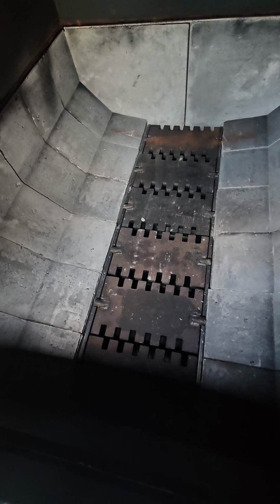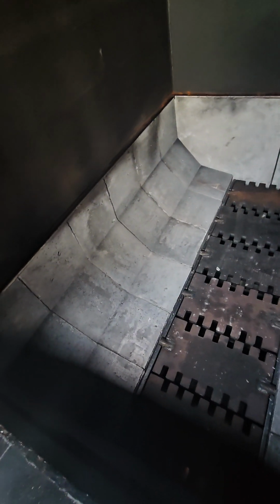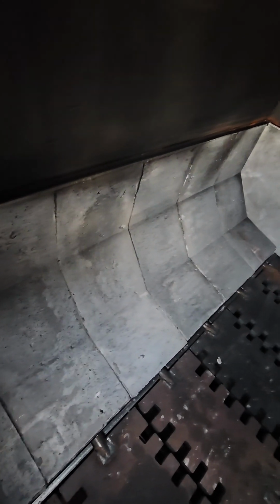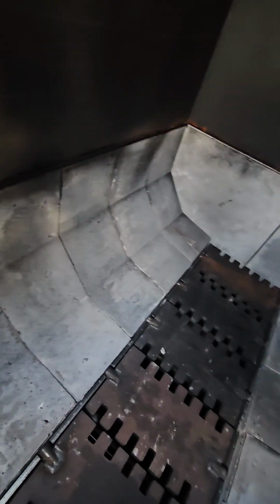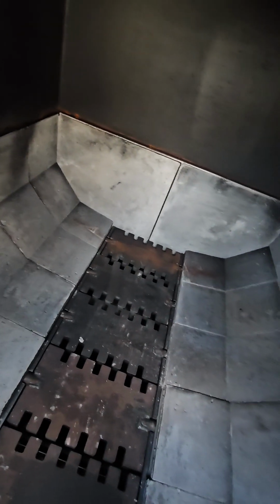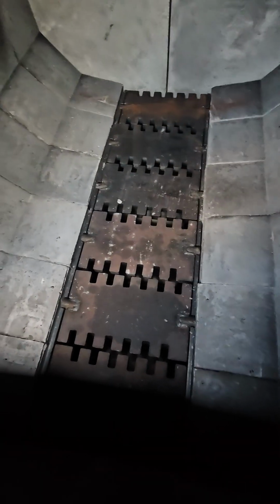But the biggest thing on these is that dry base. One reason why it's important is because when you surround your firebox with a water jacket, you're sucking that heat out of that fire. This one is kind of like an added heat absorption with that refractory brick. It's going to hold that heat in there. It's going to give you a more efficient burn. What else it does is, since your water jacket doesn't start until you get to the top of that refractory brick, it's going to keep that ashes away from your water jacket.